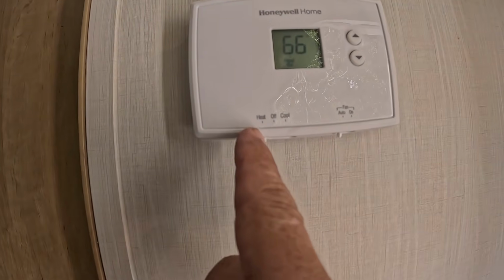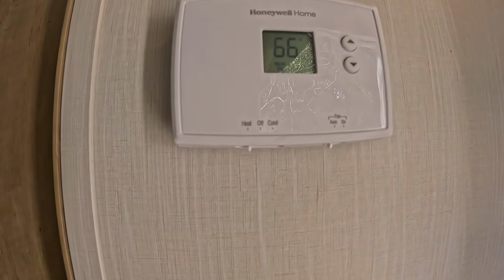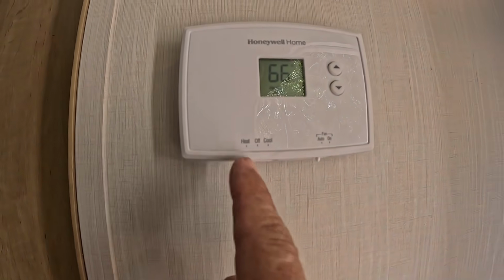All right, I've been waiting on this for like 5 minutes and the contactor has not come on. I'm beginning to wonder if that thermostat is programmed correctly. It wasn't wired correctly, so it's not out of the realm of possibilities. Okay, I can tell by this right here, heat off and cool. I have no option for emergency heat. This thermostat is not meant for a heat pump, and that's why it's not coming on. I'm gonna have to replace the thermostat anyway.